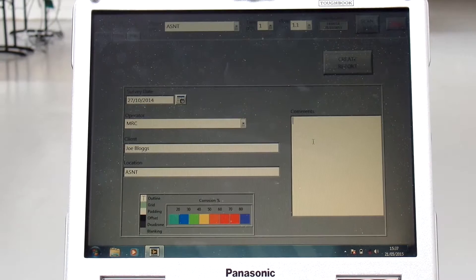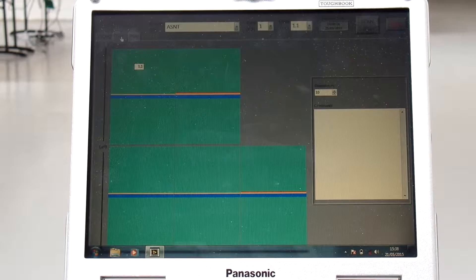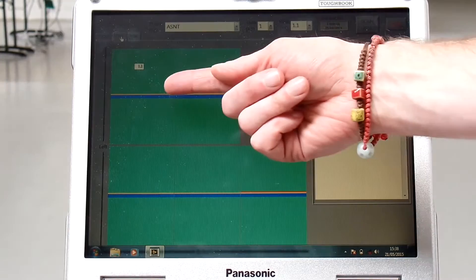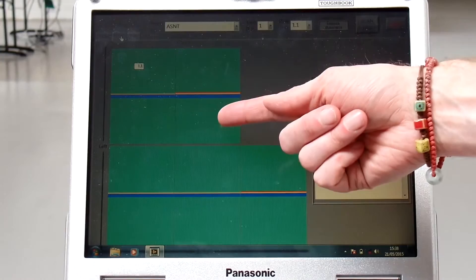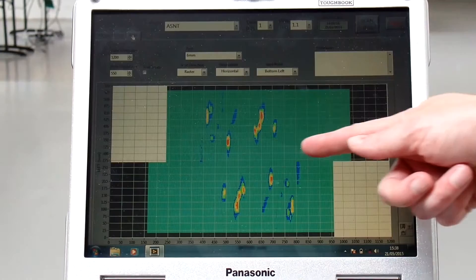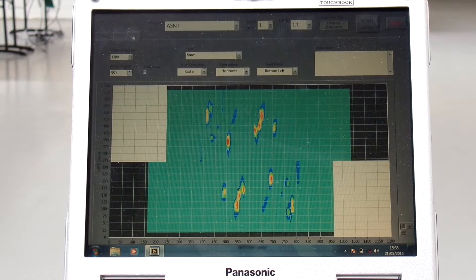The tank tab shows a top-down topographical view of the tank that is being inspected. This dynamically changes as more plates are scanned and incorporated into the inspection data. The color bars on each plate show the percentage of the surface area of the plate at that depth. The plate tab shows in detail the corrosion map of each scan pass that has been taken to map out the corrosion on the plate that is being inspected.